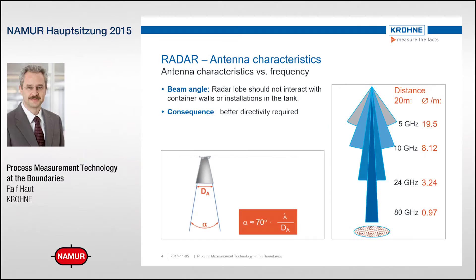Different antenna characteristics apply at different frequencies. One key condition is that the radar lobe should not interact with container walls or installations in the tank, which requires better directivity. The aperture angle is approximately 70 degrees multiplied by the wavelength divided by the diameter of the aperture — a formula that defines the width of the radar lobe.